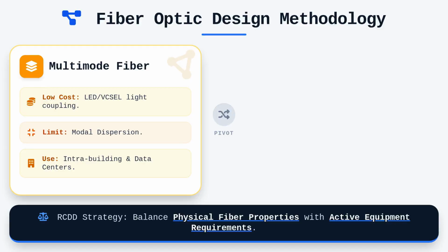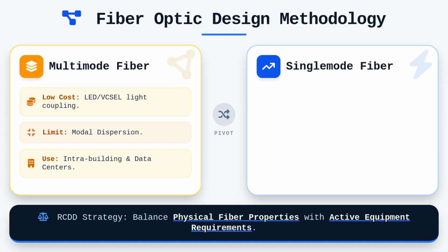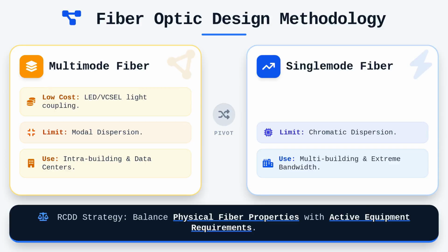If your design requires a link spanning multiple buildings or extreme bandwidth requirements that exceed the capabilities of laser-optimized multimode glass, you must pivot to single-mode solutions. Single-mode systems are limited primarily by chromatic dispersion of the signal itself rather than by the power output of the transmitter, allowing for nearly limitless future-proofing.